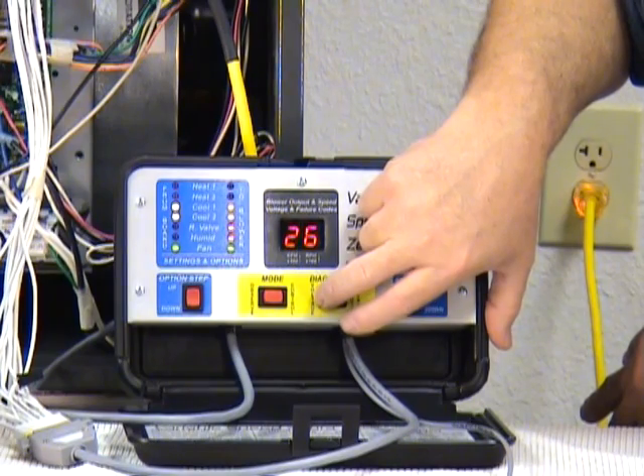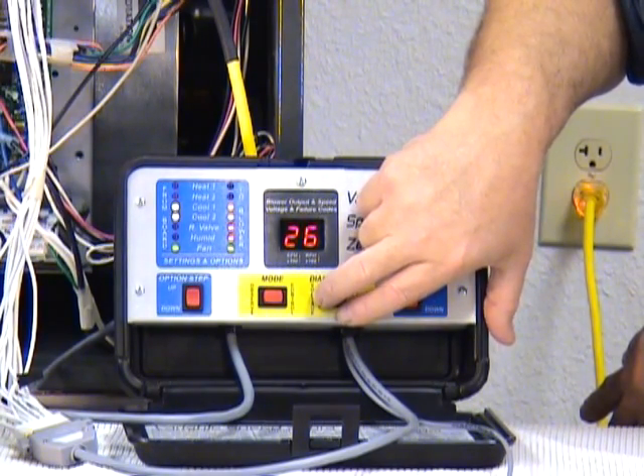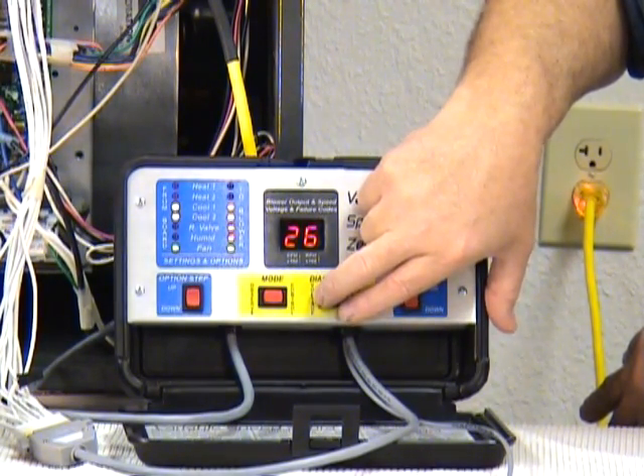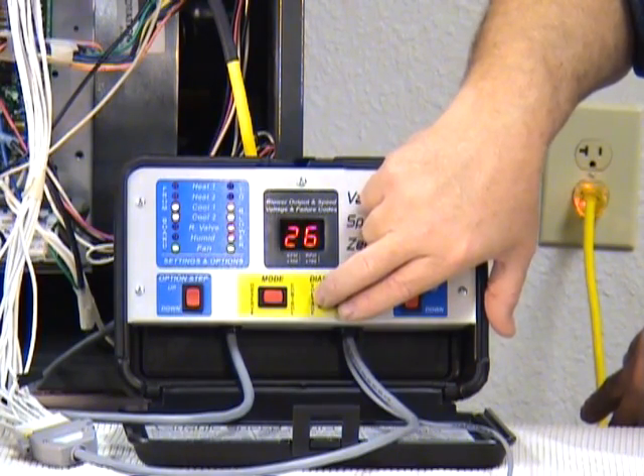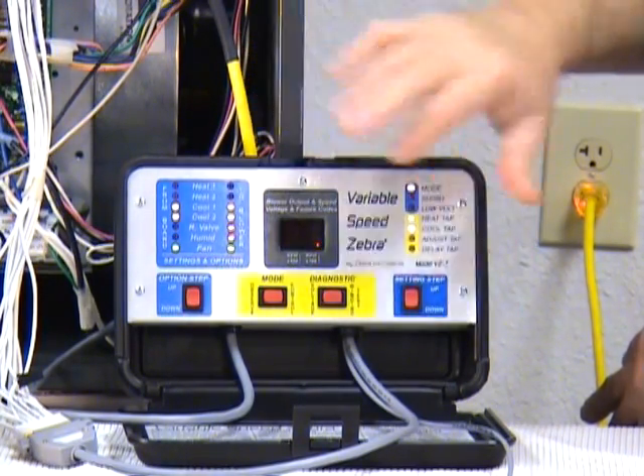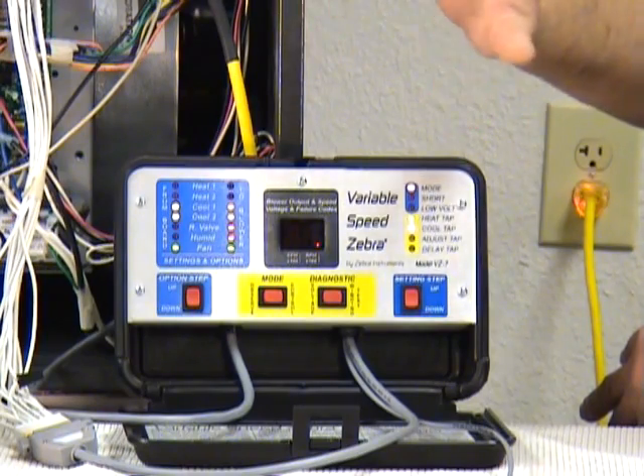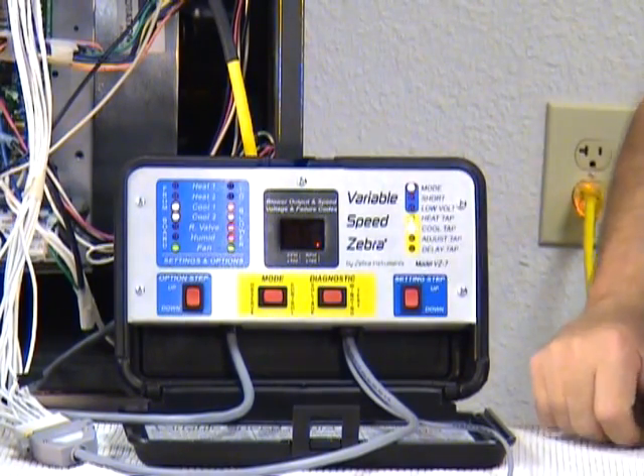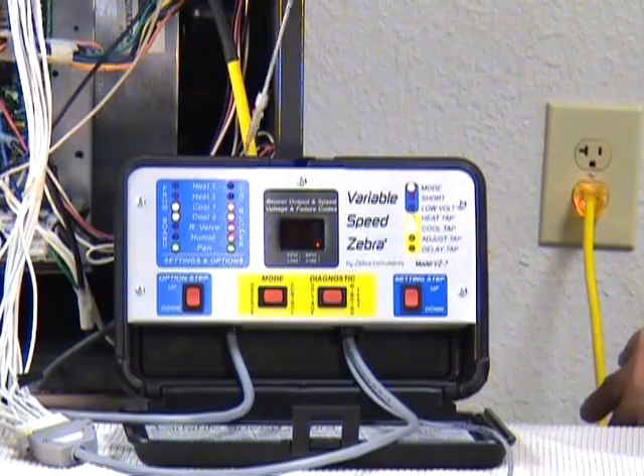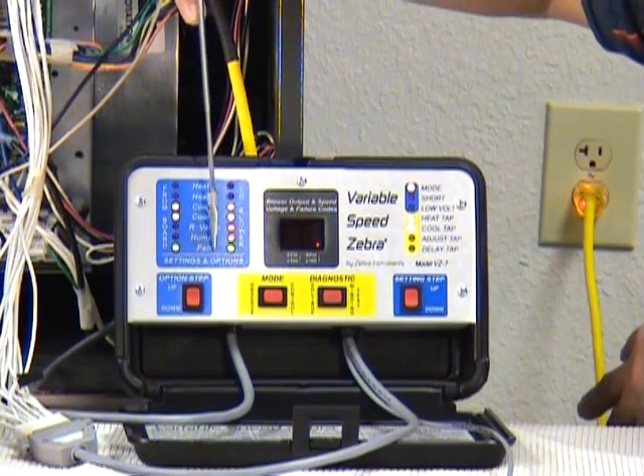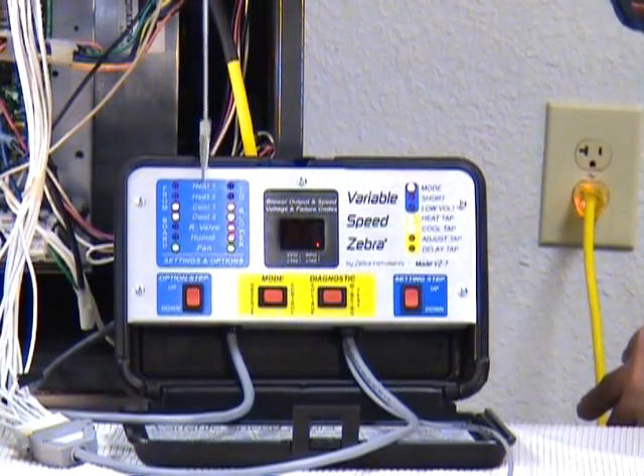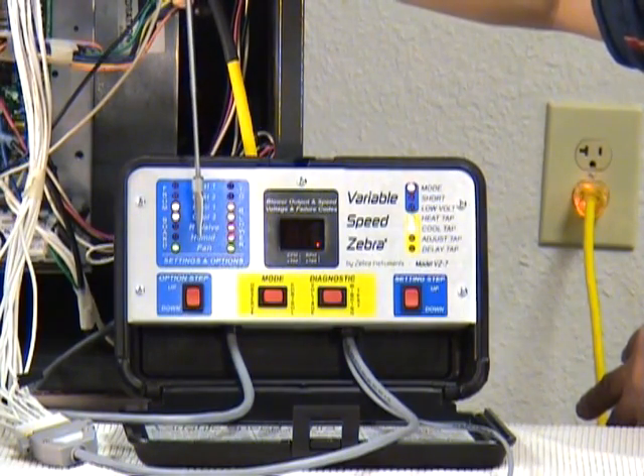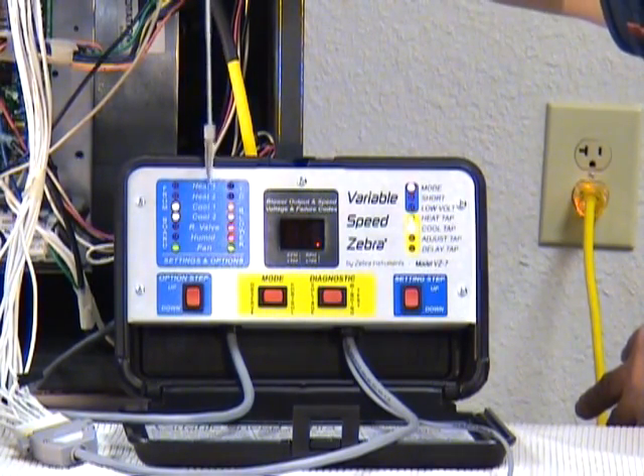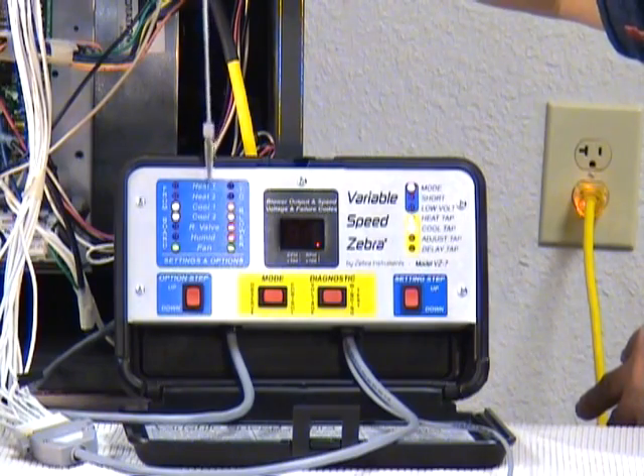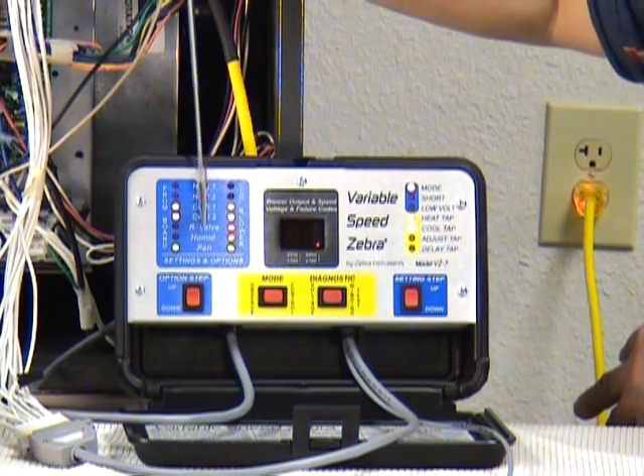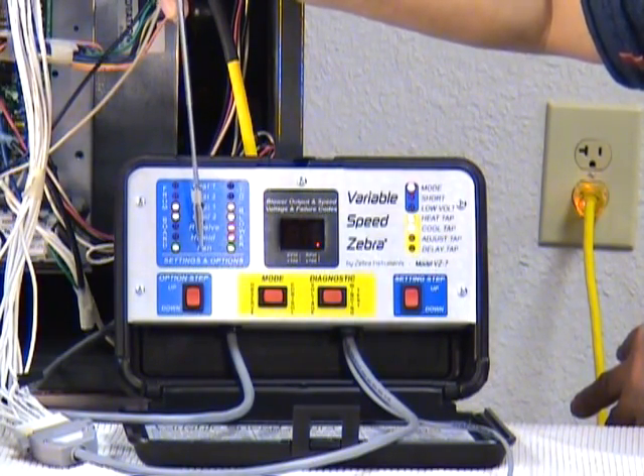Anything under 30 should be sufficient for that motor to be very happy, and as long as it's over 21 volts, that motor should be receiving enough voltage on the low voltage control circuit to process the signals properly. So there are 7 signals that your system can change going into that motor to give it commands about what speed to run at: the 2 heats, the 2 cools, the reversing valve, the humidistat, and the fan.